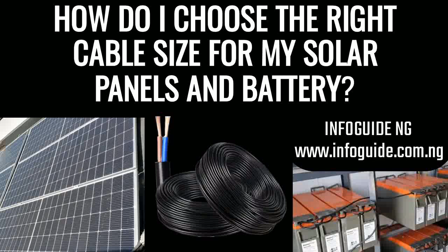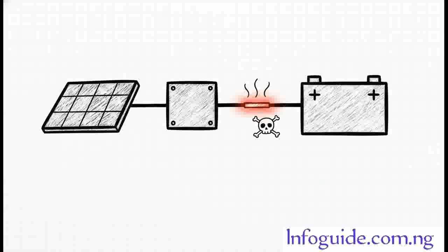So I've got to ask you, is your solar system secretly suffering? You can have the absolute best panels on the market, a top-of-the-line inverter, the whole shebang. But if the wires connecting everything are wrong, you're not just leaking power, you could be creating a massive safety hazard without even having a clue. Because that's really the bottom line here. A cable that's too small is the silent killer of your entire solar investment.